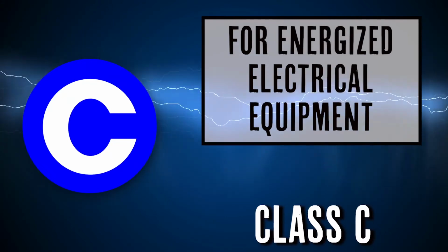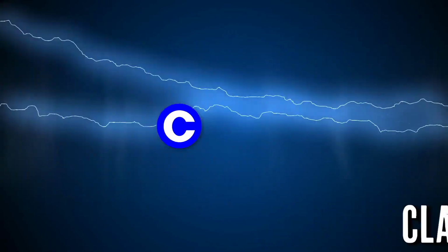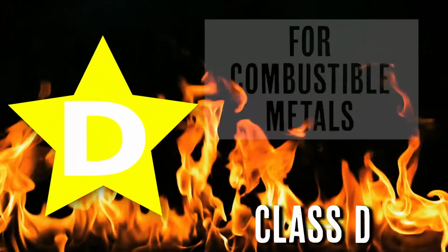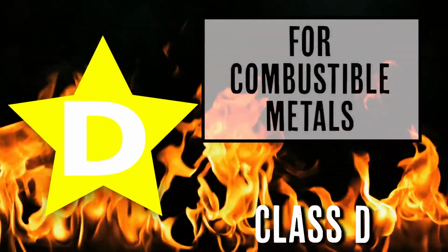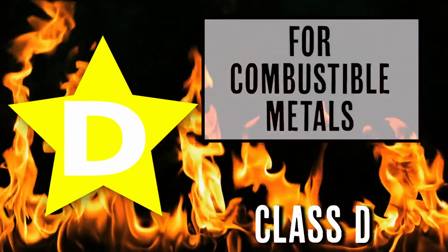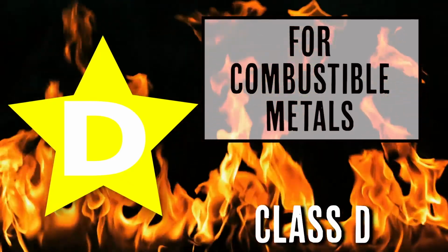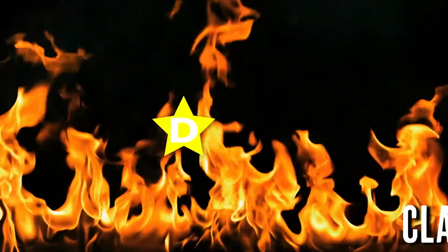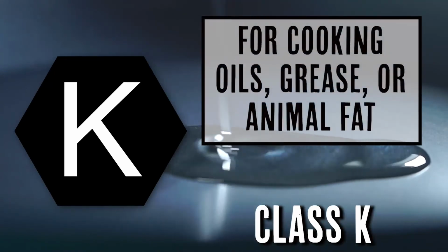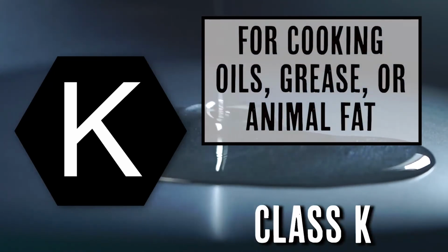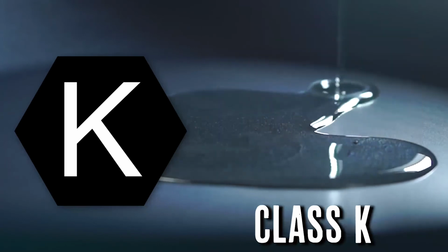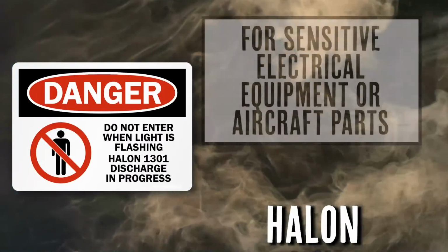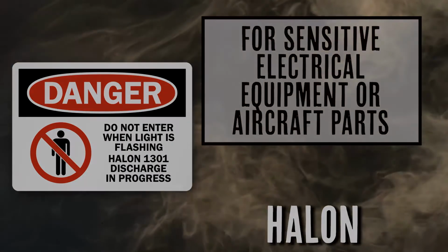Class C, for energized electrical equipment such as microwaves or computers. Class D, for combustible metals such as magnesium, potassium, or any combustible metal alloys that can react explosively to water. Class K, for cooking oils, grease, or animal fats like those you'd find in a kitchen or restaurant setting. And Halon, for sensitive electrical equipment or aircraft parts.